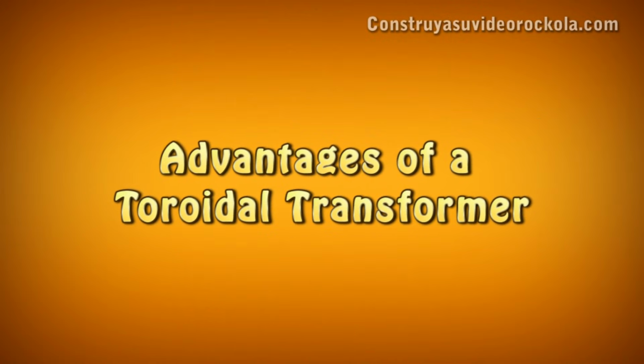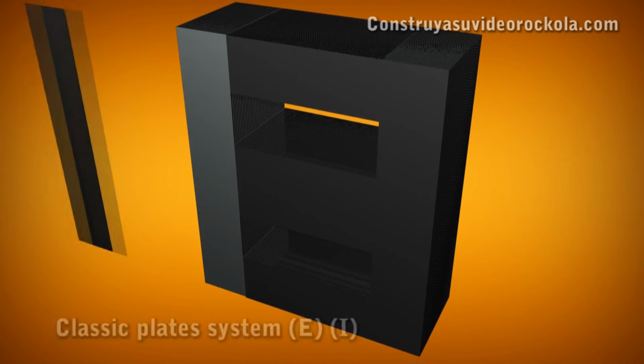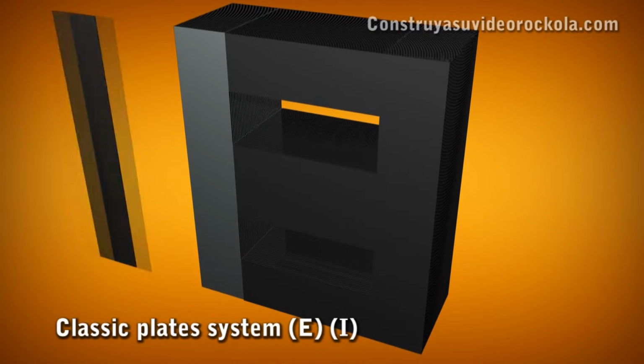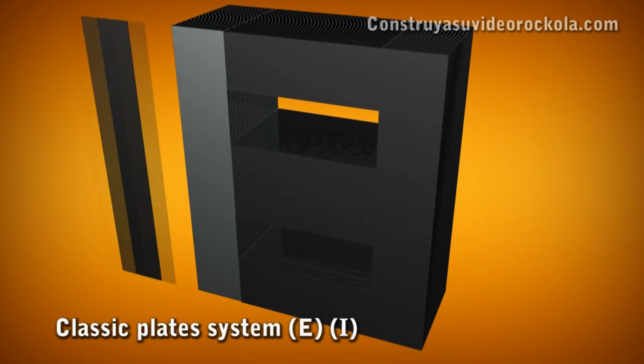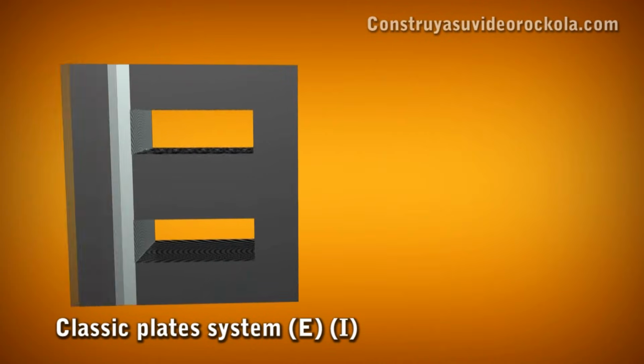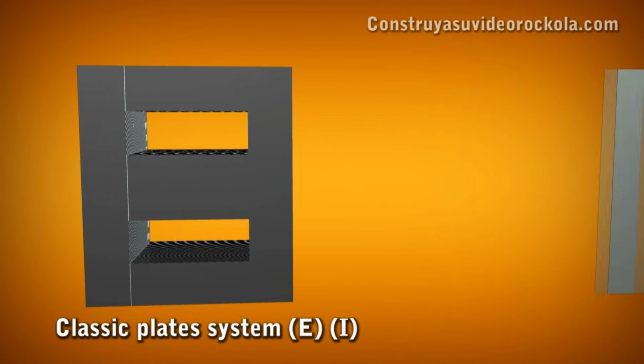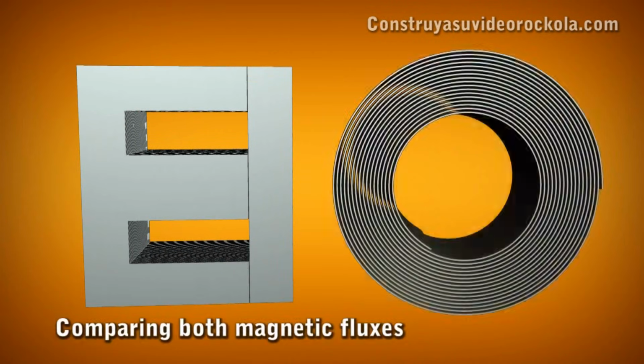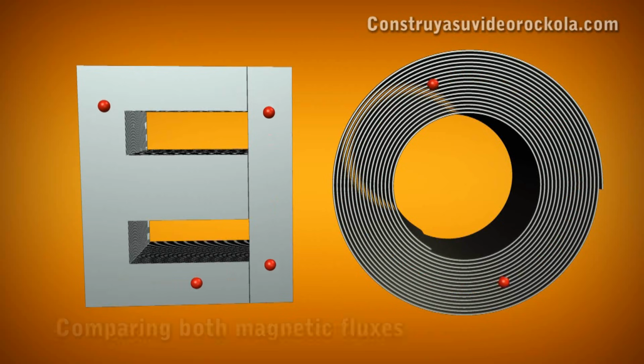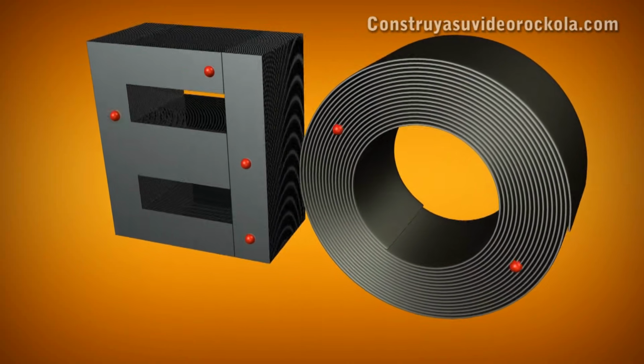Advantage of a toroidal transformer. In classical transformers, with cores made of E-shaped plates and I-plates, the flow of the magnetic field has to turn around to follow the profile of the plates, forcing the electrons to leave the junction of the E plates with the I plates, generating a magnetic flux leakage. Meanwhile, in toroidal transformers, the magnetic flux runs through the core, always rotating in the direction of its circumference, meaning in the same direction as its lamination.